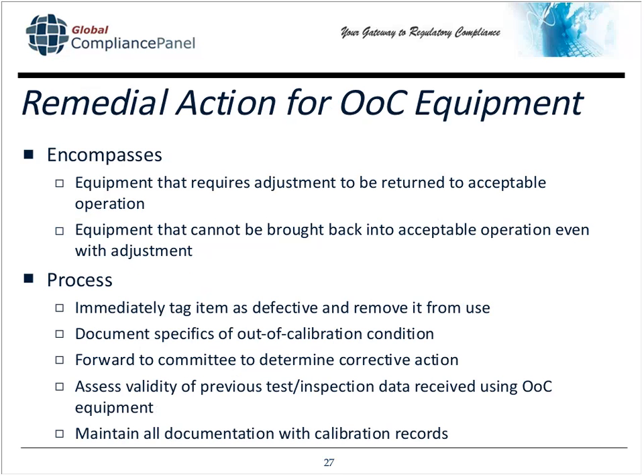What do you do if you have a piece of equipment that is out of calibration? This remedial action will encompass anything that required adjustment to be returned to acceptable operation, and equipment that can't be adjusted at all. This is just broken. The process is to tag the item immediately and pull it out of use, and make sure when you remove it from use, you record this in your internal calibration database or spreadsheet. You want to document the specifics of the out of calibration condition. How far out of calibration was it?